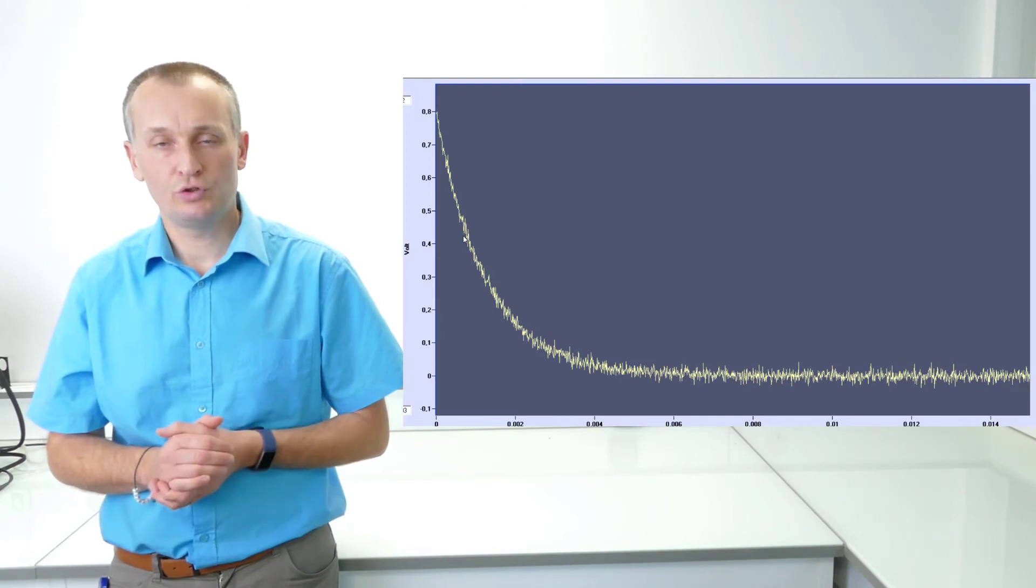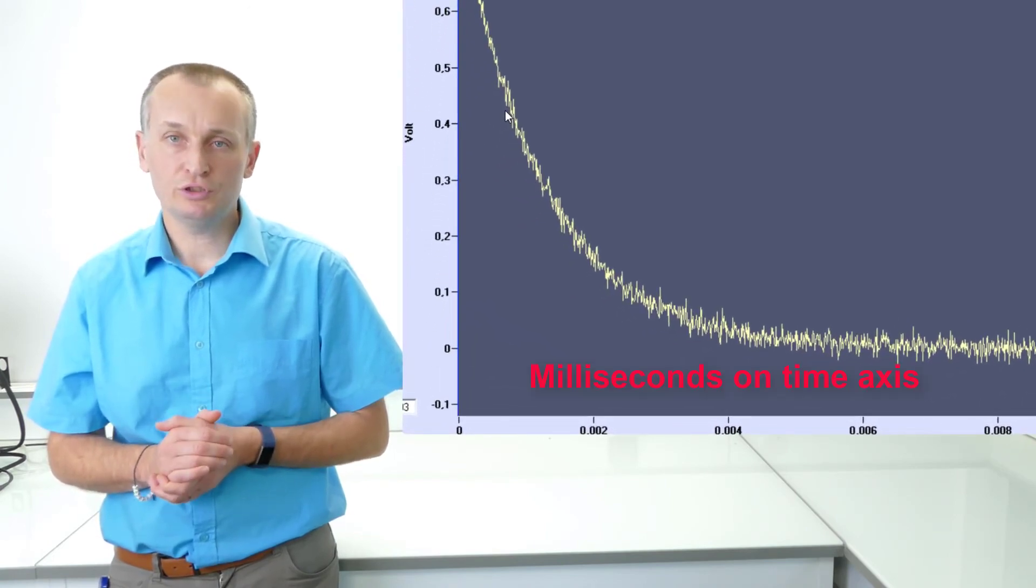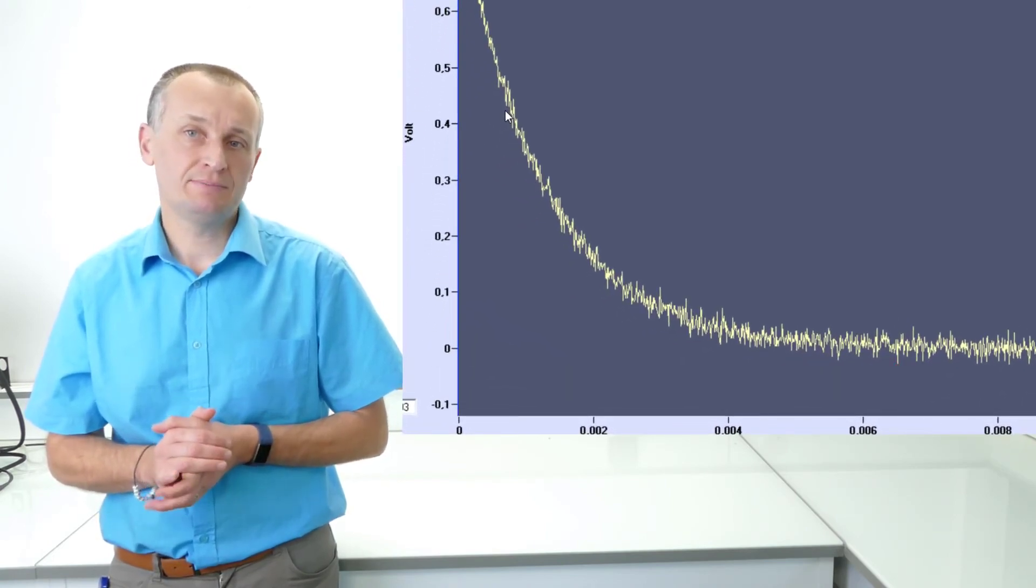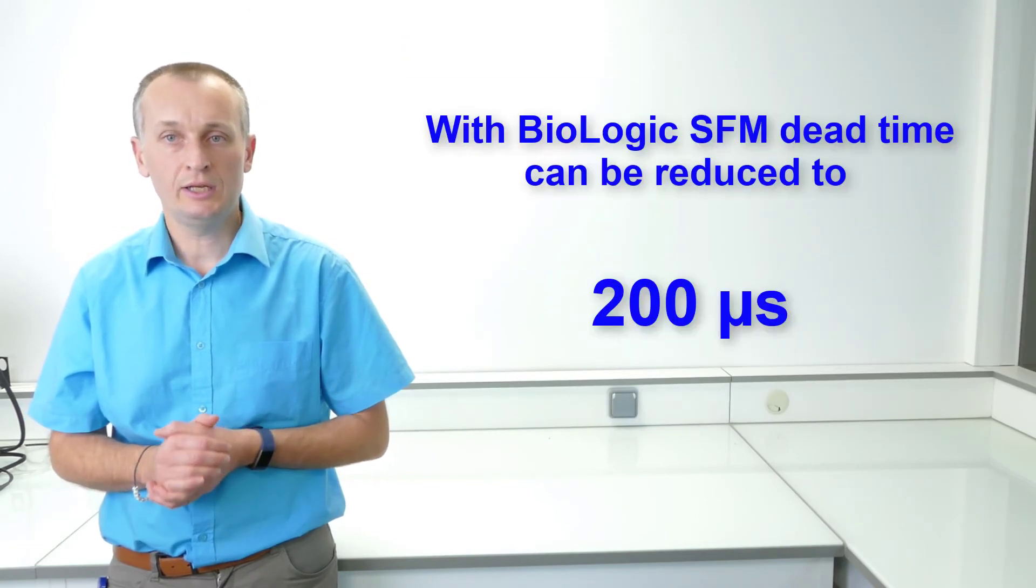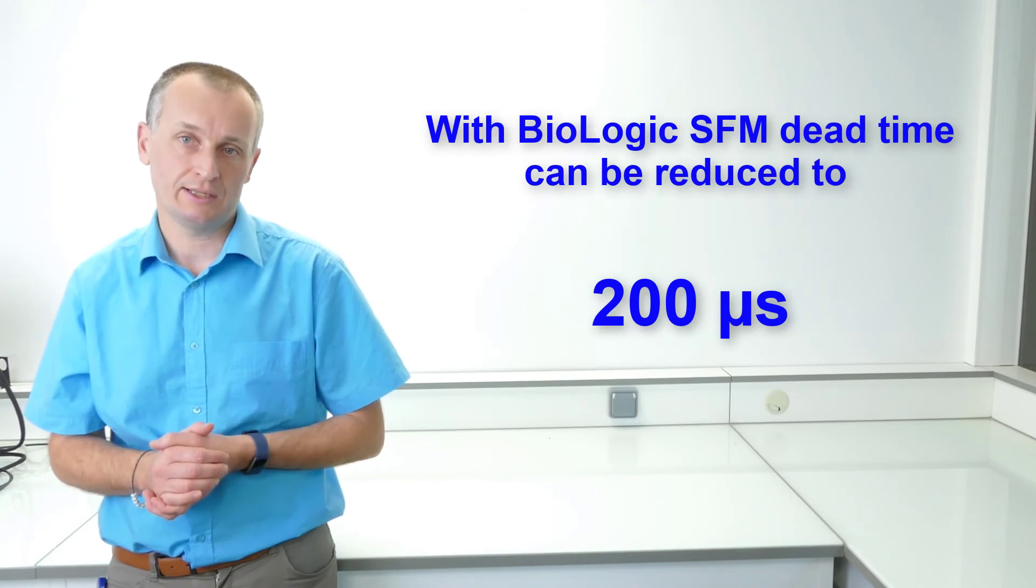The dead time of a stop flow is directly linked to the size of the cuvette you are using. In most configurations, the dead time is between 0.5 ms and 1 ms. But using the micro-cuvette accessory, you could reach 200 microseconds dead time.